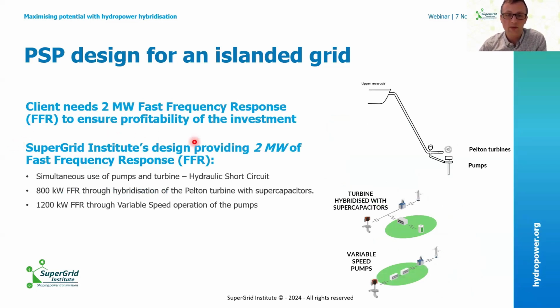To provide these 2 megawatts of fast frequency response mostly in off-peak hours, we suggested to use the existing installations, the existing design, which is made of Pelton turbines with separate pumps, and to run the pumps and the Pelton turbines simultaneously. This is what we sometimes call a hydraulic short circuit. You might be familiar with this terminology. It's been demonstrated in the X-Flex Hydro project recently in Europe. We suggested using this and providing 800 kilowatts of fast frequency response through the hybridization of the Pelton turbines with supercapacitors, because, as we'll see a bit later, the Pelton turbines could not provide such a response in 2 seconds.